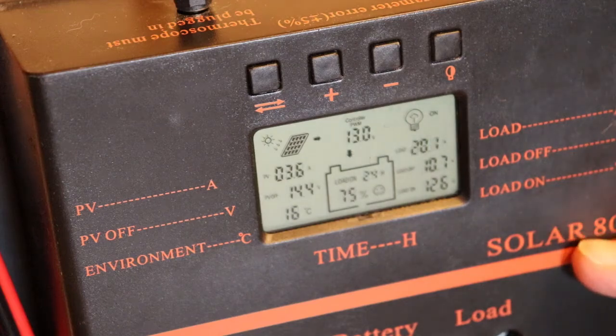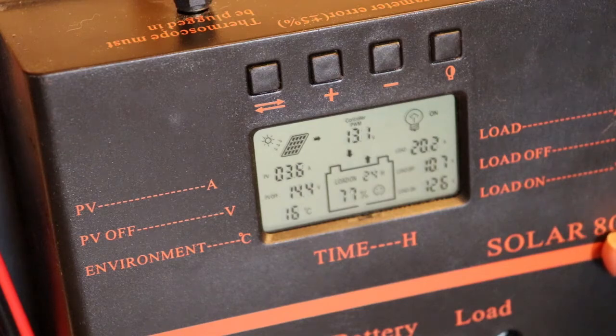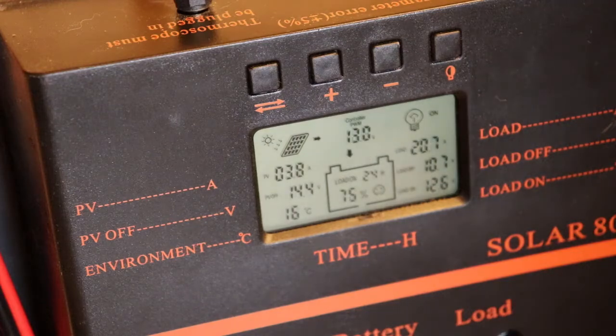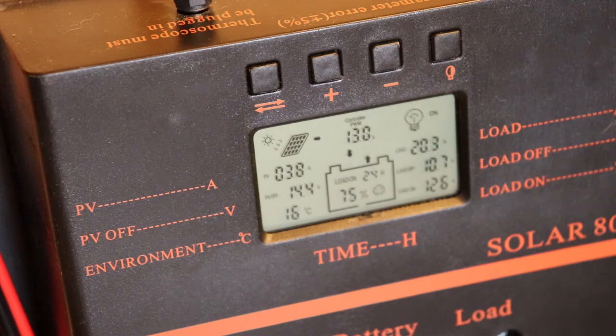Now, on this unit, I needed to make a clarification. This is 80 amps for 24 volts. This unit is a 12 or 24 volt DC unit. The difference is that when you run it in 12 volt capacity, you're only going to get about 1,000 watts. When you run it in 24 volt capacity, you're going to get about 2 kilowatts of power. The higher you go in voltage, the more efficient your machine is. And I actually could just put those batteries in series and run them from the ground to the middle post, and a 24 volt system would be more efficient. However, when you do that, you don't get the exact voltage you would get if you ran it across the 12 volts. It could be a little higher depending on the battery's BMS system for balancing out the voltage.